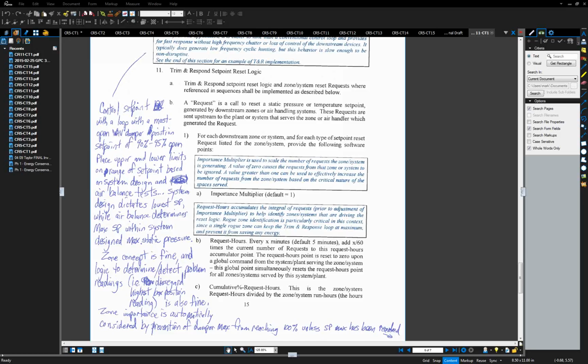We were approaching it a little bit differently, in that we trend, and we also check and alarm when we get these groups. We put it into groups, basically like zones, and then we take the maximum damper position from each of those and set the set point to 90%. But then on the other side of that, if it goes above a certain percent for over a certain amount of time, then we alarm it to say there's something wrong, we're not satisfying that group anymore. So it's a similar type of thing, but it basically says we have to have everybody satisfied, rather than some being more or less important than others. And I can see where there could be some advantages to doing it this way.